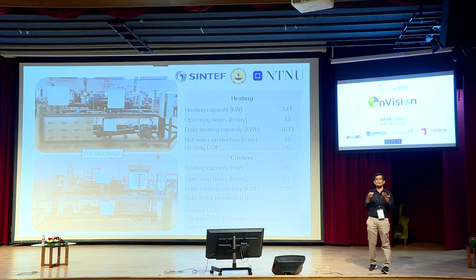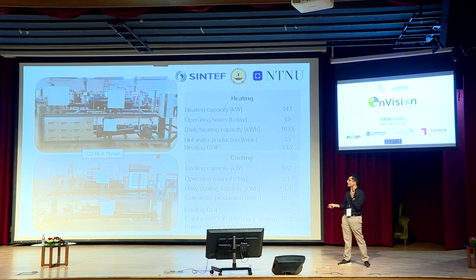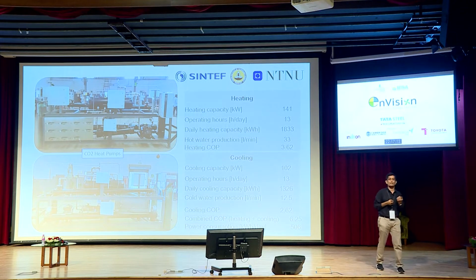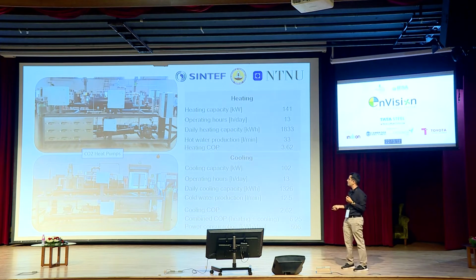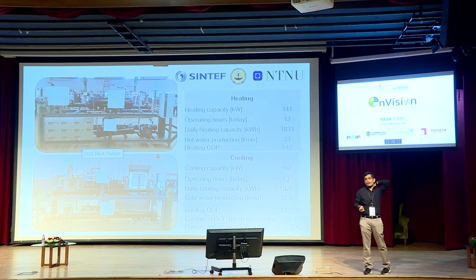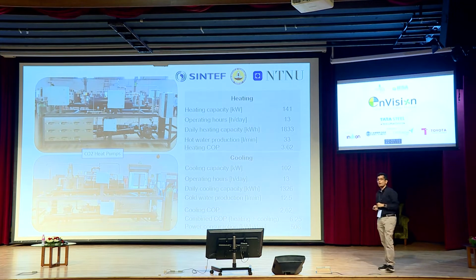CO2 is an emerging technology, primarily for two reasons. One is that it's a natural refrigerant. Synthetic refrigerants bring challenges like ozone depletion and high global warming potential. CO2 is emerging, but it's an expensive technology, costing more than 5 times a commercial vapor compression system. Nevertheless, the system we're building allows us, in a single frame, to do 5-degree cooling on one side and 95-degree heating on the other.